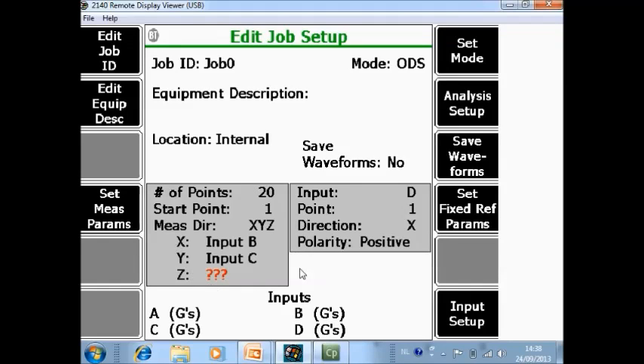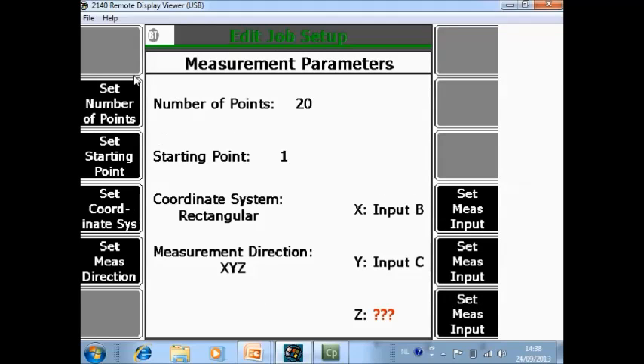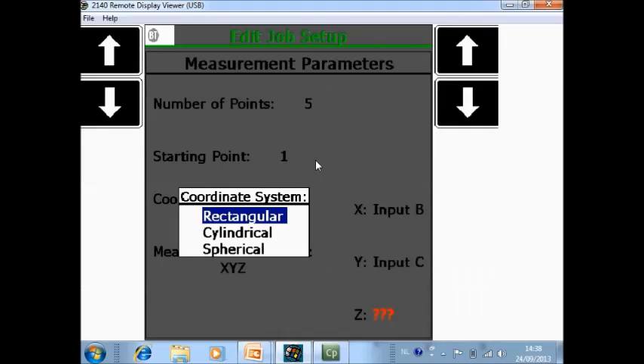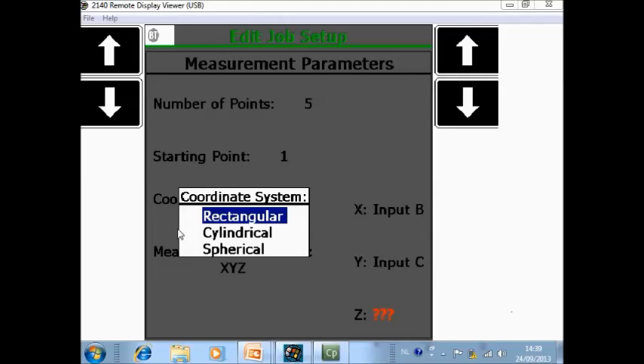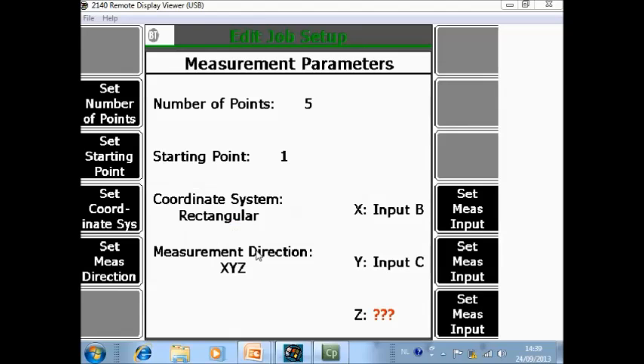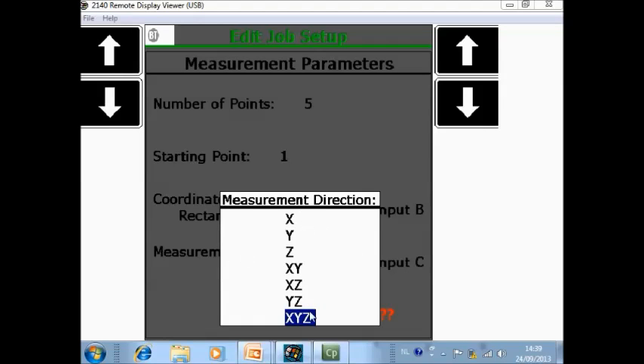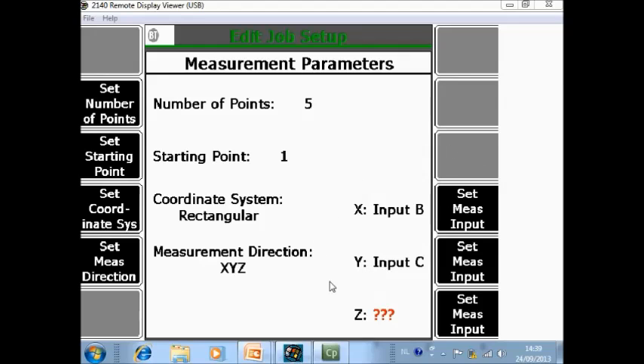Now I can configure the triax sensor and set the measurement parameters. An ODS job will often contain 100 or more data points, but for this tutorial I will measure only 5 points to simplify the structure. I will start on point 1. You can toggle between rectangular, cylindrical, or spherical coordinate systems — rectangular is normal XYZ. The measurement direction we will use is XYZ. For the input we specify what we explained earlier: your X is on A, your Y is on C, and your Z is on B.